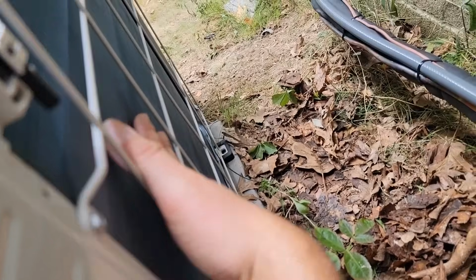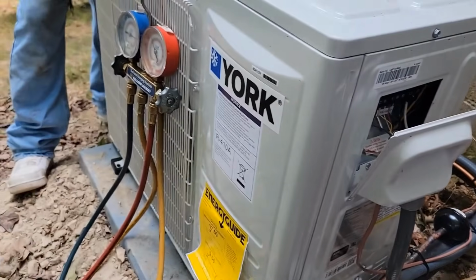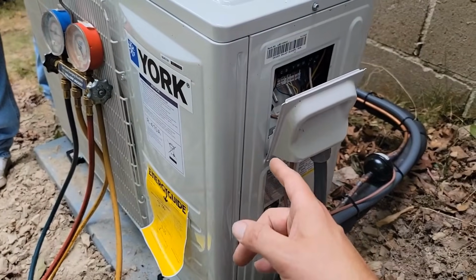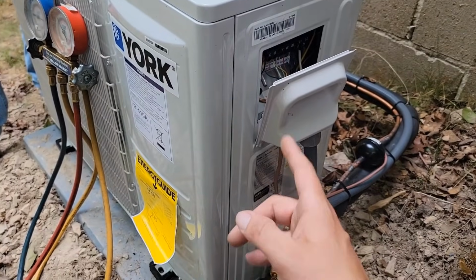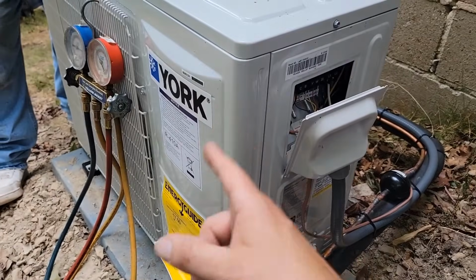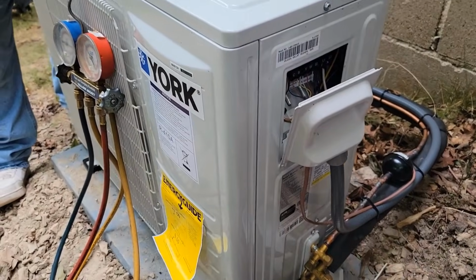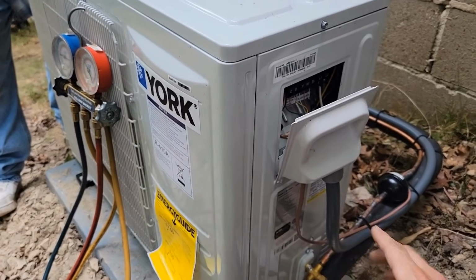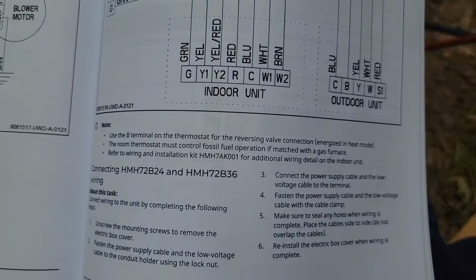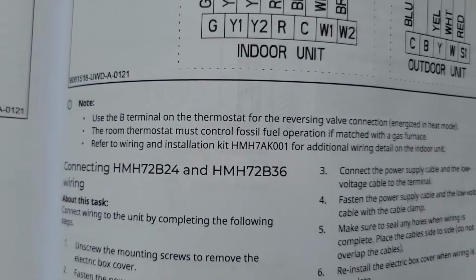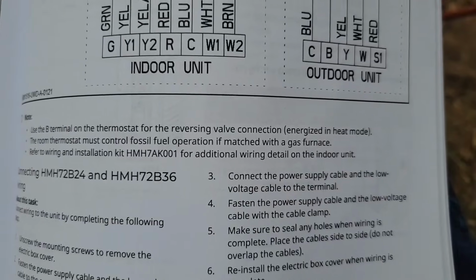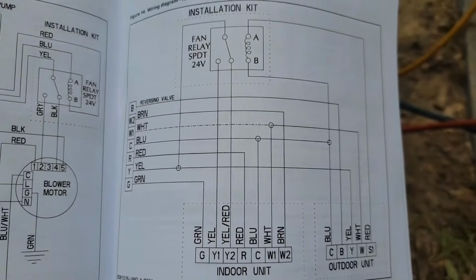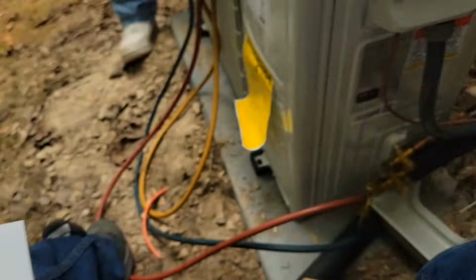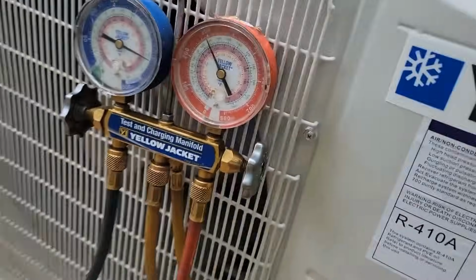Liquid line's warm, suction line's warm. Coil feels kind of cold. It must be in the heating operation. So it may need to have the reversing valve energized differently than what I'm used to, which is energized in the cooling mode. It may need to be energized in the heating mode. So that's just a simple thermostat adjustment. This is why it's super important to read your manual. It says, note, use the B terminal on the thermostat for the reversing valve connection, energized in heating mode. Looky there. All right, let's go make the switch and then turn the unit back on.